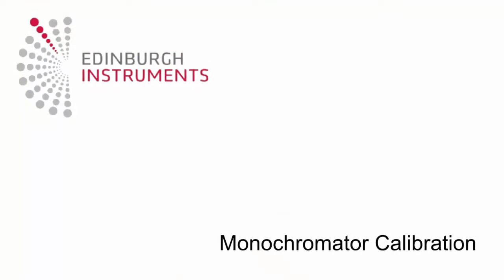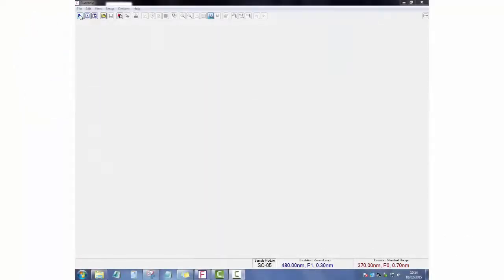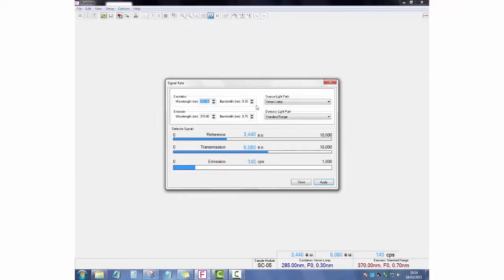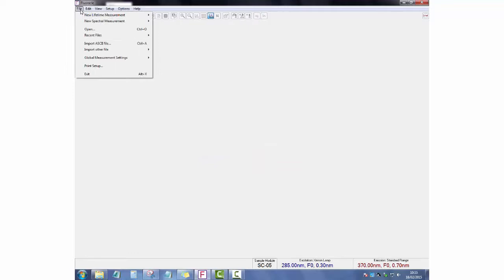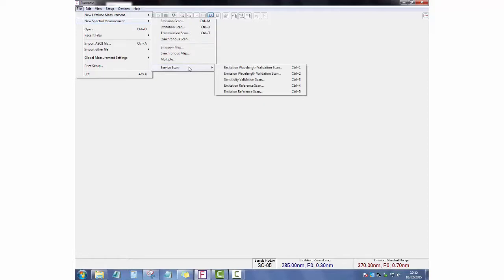We will now show you how to go through a process to ensure that your excitation and emission monochromators are properly calibrated. Firstly, set the excitation bandwidth to 0.3 nanometers. Then go to File, New Spectral Measurement, Service Scan, Excitation Wavelength Validation Scan, or Control+1.